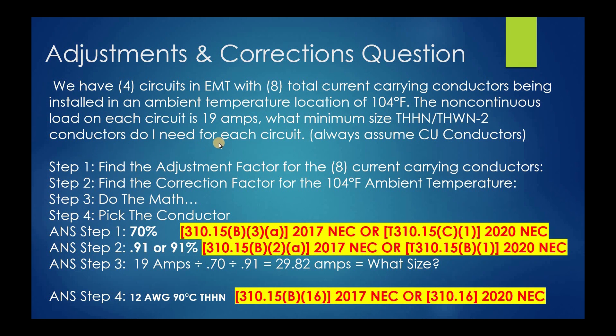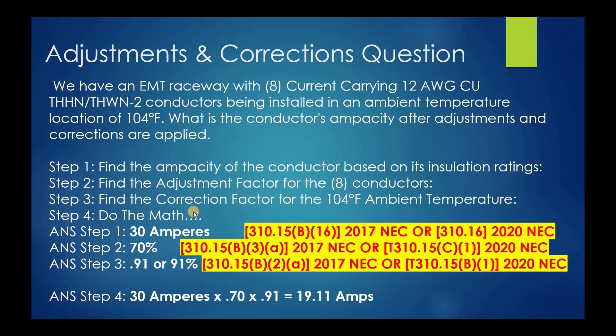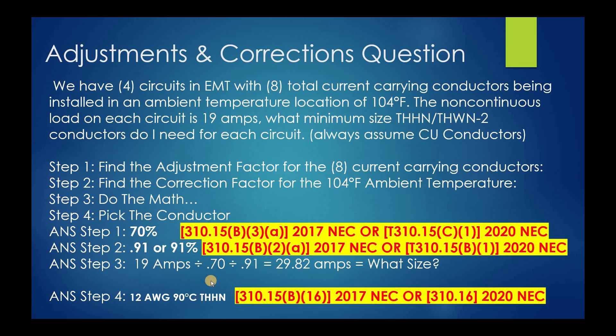Now there are some steps to go through to solve this. In the previous example, we already started with 12 gauge and went to Table 310.15(B)(16), starting with the 30 amps under the 90-degree column and using multiplication to work our way down. This is a little different — we're going to use division because we're given the actual load, and we'll work our way up, applying adjustment and correction factors to determine what conductor we need to find in the 90-degree column.